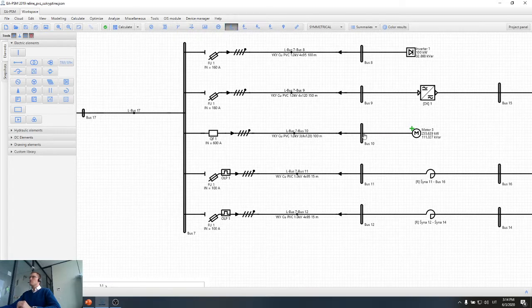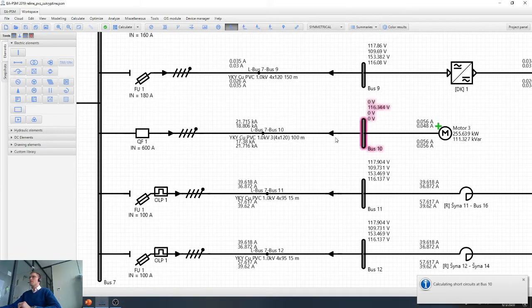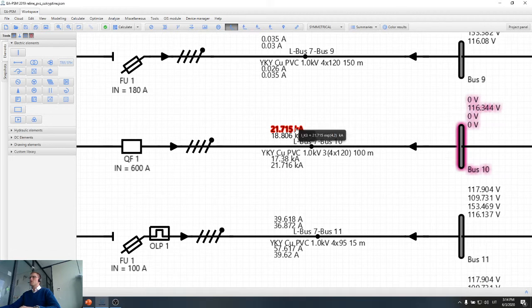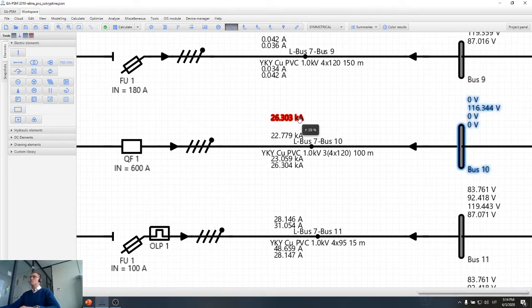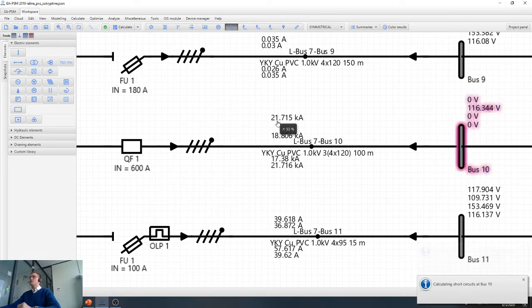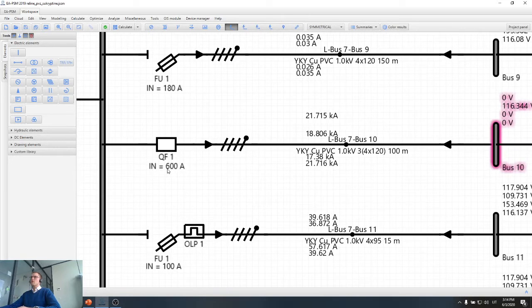So for example, let's calculate a short circuit in our network. I will choose this bus 10. So we see that we have short circuit currents calculated in the minimum mode. So minimum short circuit current in three-phase short circuit level is 21,700. Yeah, so this is the short circuit current. And here is our protection device, whose nominal current is 600 amps. So now we can compare our protection device nominal current with the short circuit current, and we can clearly see that the nominal current of the protection device is much less than the short circuit current. So which means that our protection device will be sensitive enough because its pickup current will be much smaller than the short circuit current.